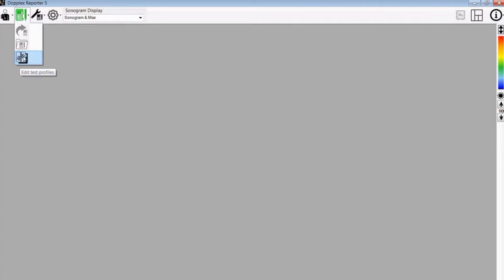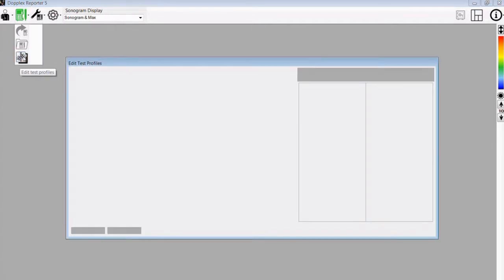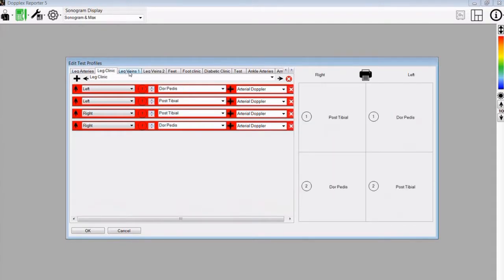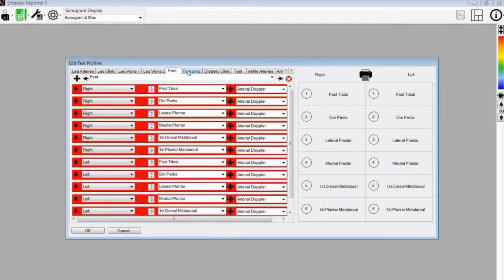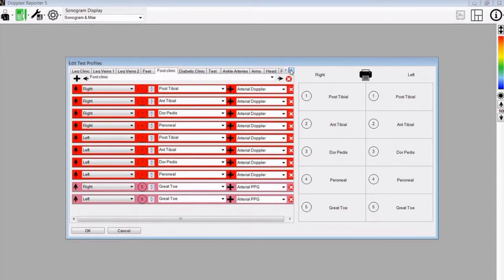To edit the test profiles, go to the Doppler menu and select the Edit Test Profiles button. The different preset test profiles will be shown. Here you can see tabs along the top of different profiles which have been preset in the software. You can select one of these which matches the type of test you are conducting, or you can start a new test or set a new profile.